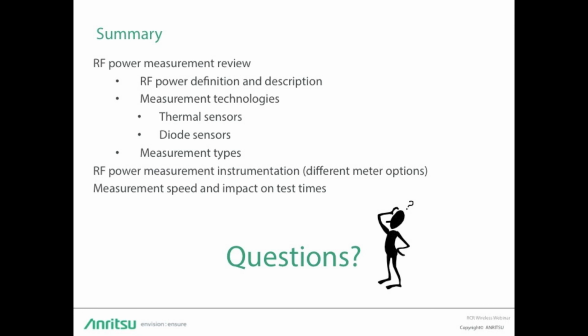How does video bandwidth factor in when selecting a true RMS sensor? Yeah, that's a good question. We actually get that question quite often. The important thing to remember is that when you're making measurements with an RMS sensor, the video bandwidth is mostly irrelevant. You're just making modulation independent average measurements. The video bandwidth comes into play when you're trying to make peak power measurements. The important part there is that your sensor can react quickly enough to capture the full power of the pulse, if you're doing pulse measurements, for example. So if you're looking for an RMS sensor, video bandwidth is not something that you should be concerned about.